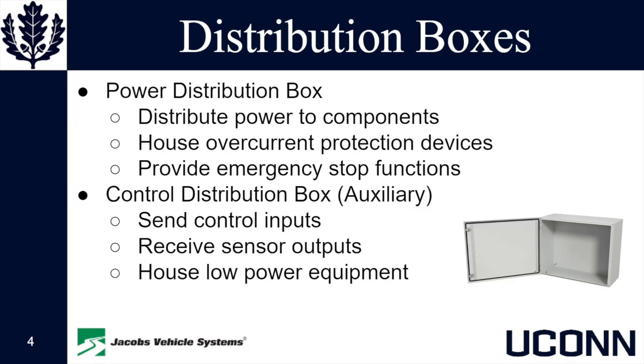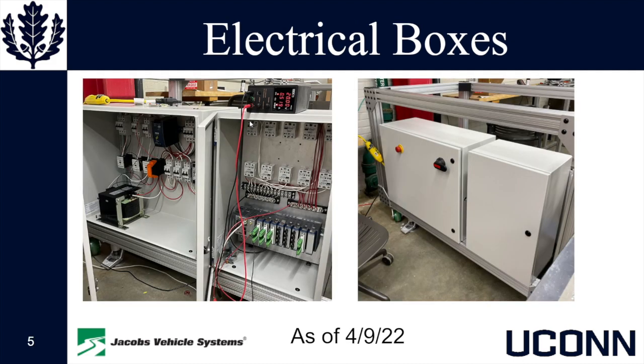For the electrical side of the project, we have designed two distribution boxes. The first of the two boxes is the power distribution box. Its primary purpose is to provide power to the stand, house the overcurrent protection devices, and provide emergency stop functions. The second box is the control box, with its primary purpose to control solenoid operation from sensor outputs, and house low power equipment. Here are our two distribution boxes mounted to the test stand from the day of recording.